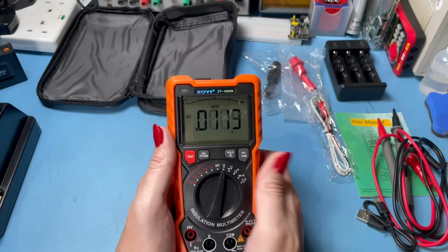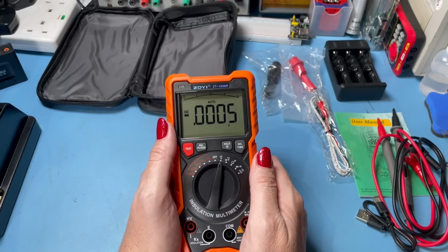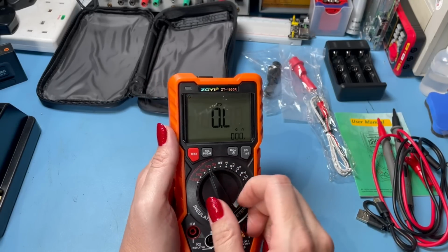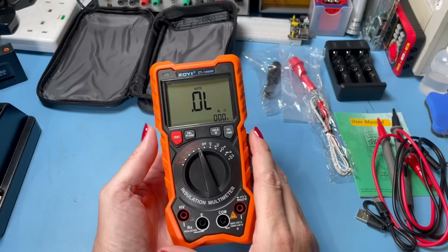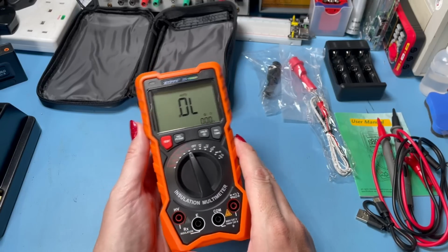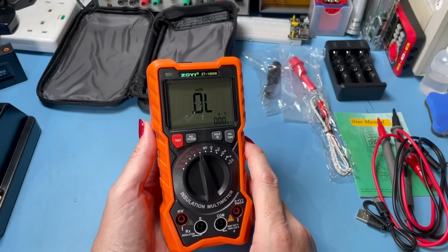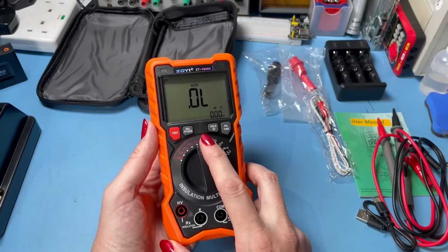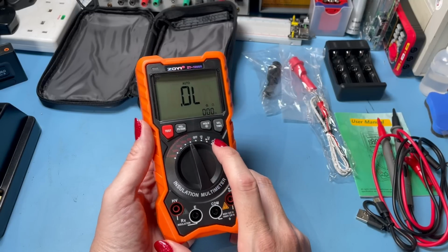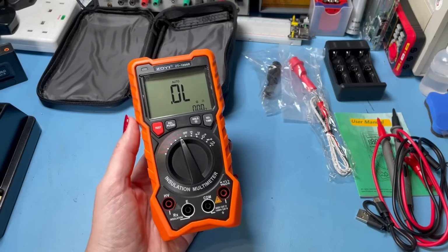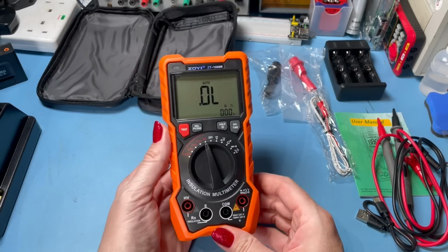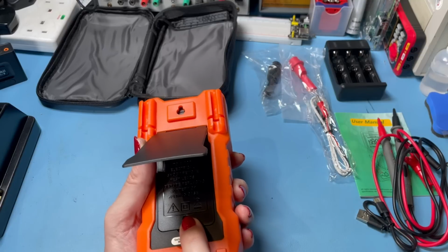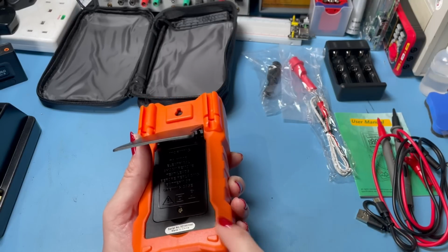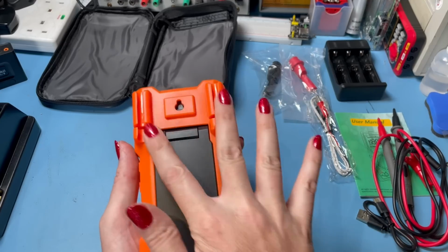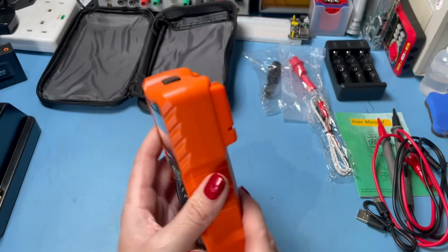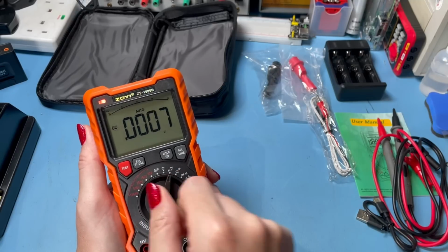But the star of the show has got to be the Megohm meter function on this. When you go into the insulation mode here, with this you can do insulation resistance testing up to 20 gigaohms. And this will give your DAR, dielectric absorption ratio, and your polarization index, PI. We'll take a look at those in a moment. It looks like you can get the batteries out without having to remove the rubber bumper, and there's a place for your probes, and there's a place to hang it up as well. So we've got our DC volts there.